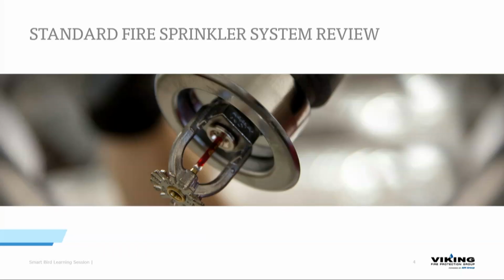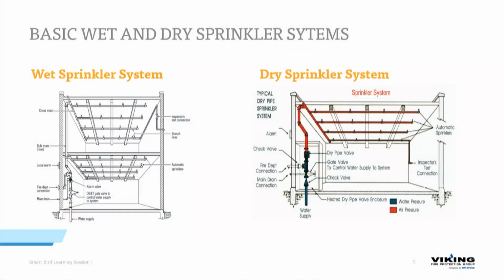All right, standard sprinkler system review. This is what we have in this building: dry systems, wet systems. This is the basics. So, wet fire sprinkler system. We have a water supply. We have our riser assembly. The OS&Y valve is a control valve. We have a flow switch, or an alarming device. We have a local alarm that would go off if that flow switch went off. Fire department connection, so the fire department can pump water into our system. This wet system is completely full of water at all times. Inspectors test off the end here. That's how we test the system to make sure that we still have water at the end of our system.